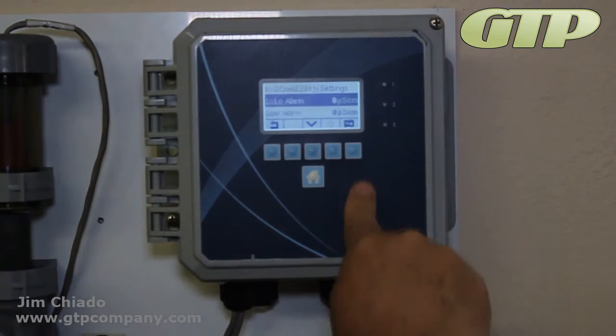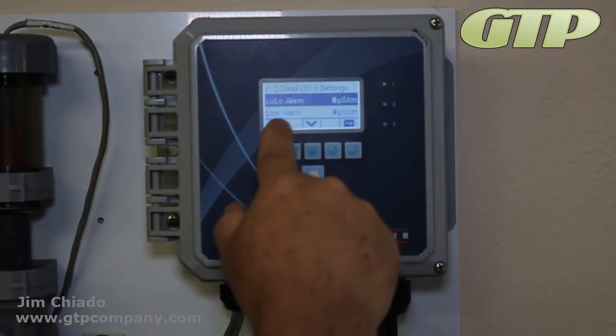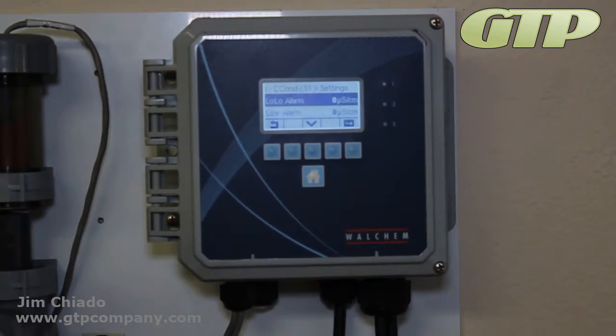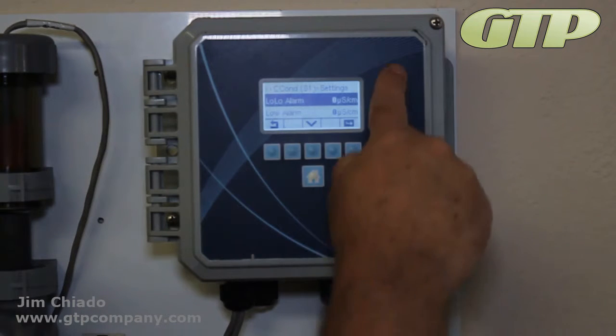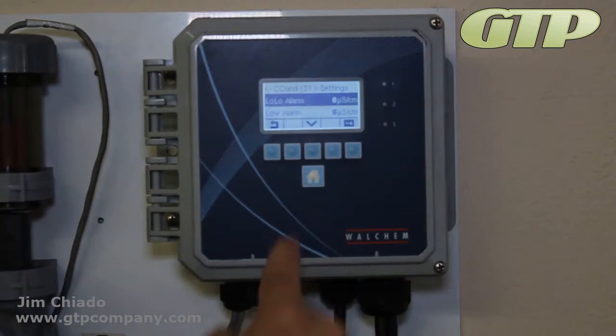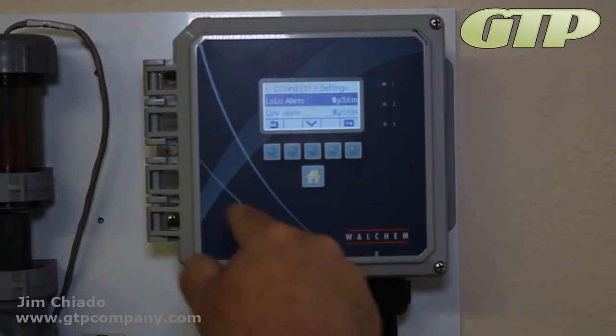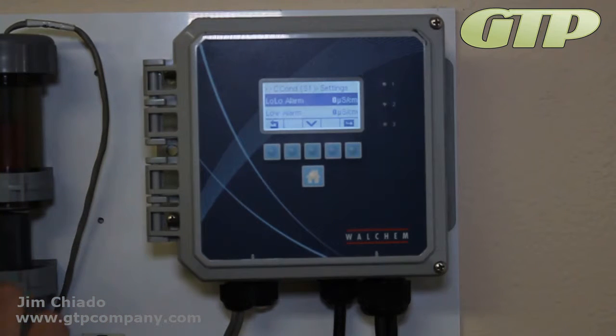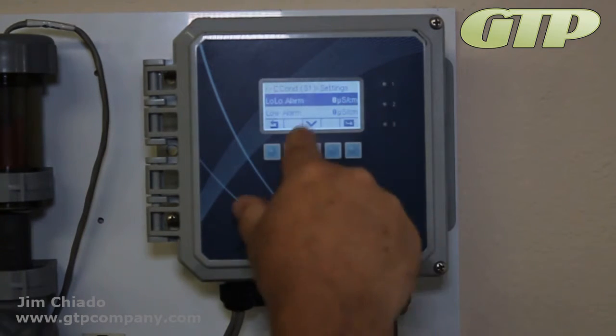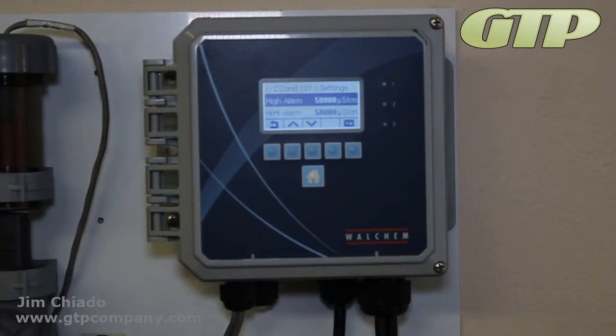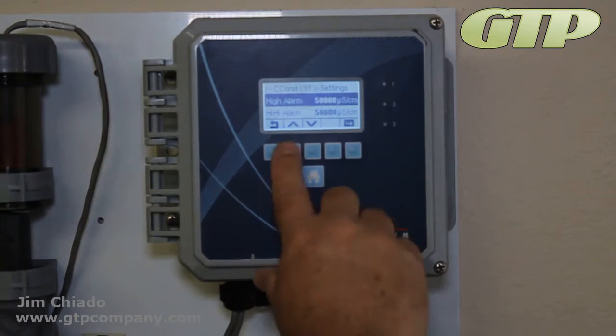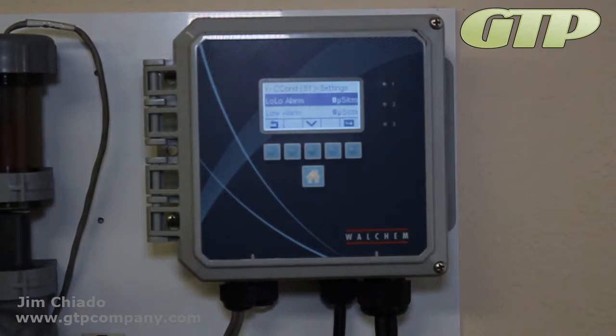Conductivity. Maintenance. Okay, we have low alarms and high alarms. These alarms are based on conductivity only. They don't turn on relays. They don't turn anything on unless you set one of your relays for alarm, which you can. It's only based on the conductivity function coming in. It's not going to open up your bleed valve. Okay, these are just settings. So, the low is at 0, and you'll see the high alarms are set at 50,000. So, you know, I recommend setting them to something that's a little bit more appropriate.